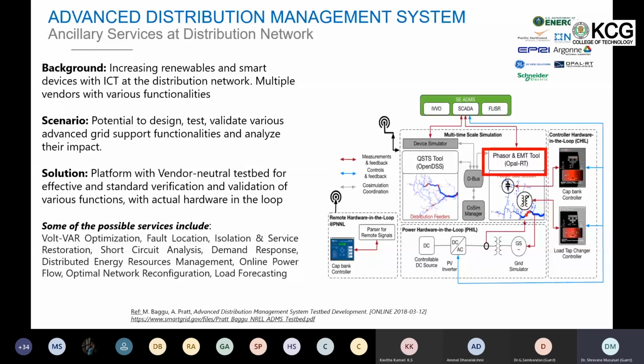A capacitor bank can have only two states, on or off. But every time it switches on or off, a huge surge goes through those capacitors, impacting its lifetime. So these capacitor banks, and even tap change transformers, have a reliability aspect: how many operations they can do within their lifetime. Even if the voltage quality is perfect, if it has too many operations, it comes close to the end of its life from a reliability standpoint.